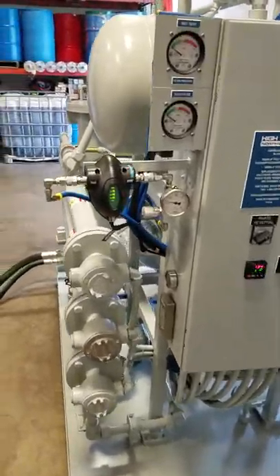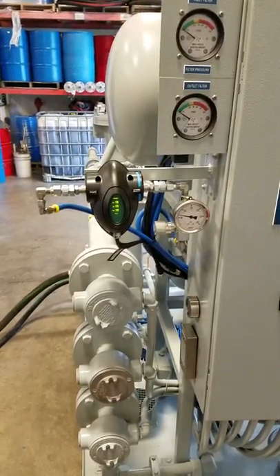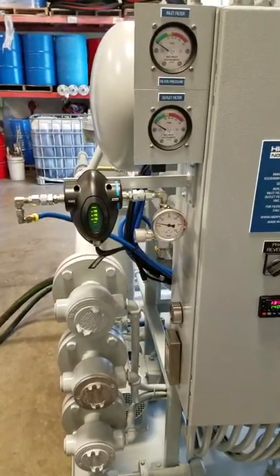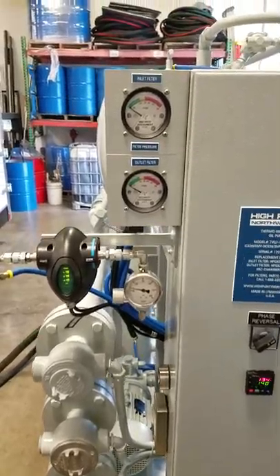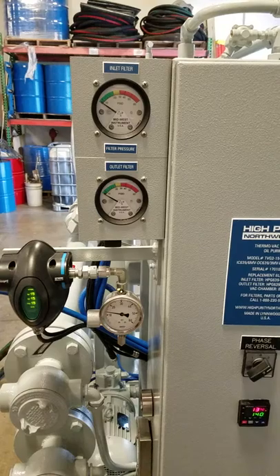It's a laser particle counter that displays ISO cleanliness codes and moisture content in real time, along with direct reading differential pressure gauges to monitor the life of the filters that are on board.